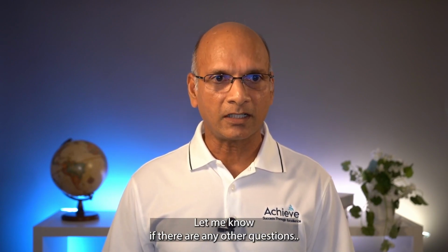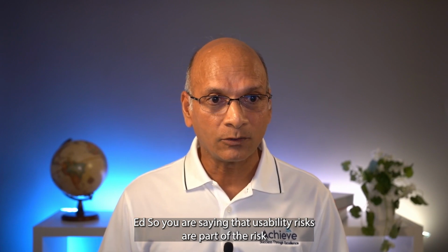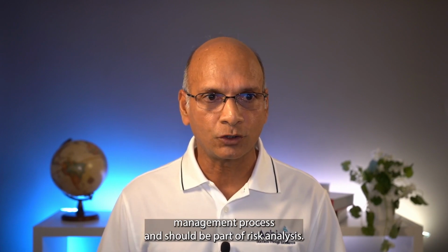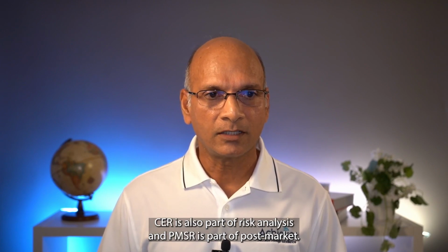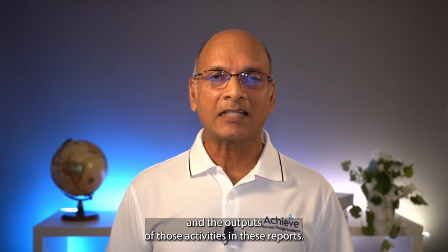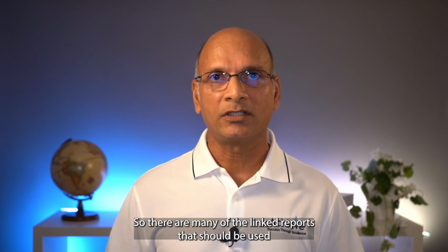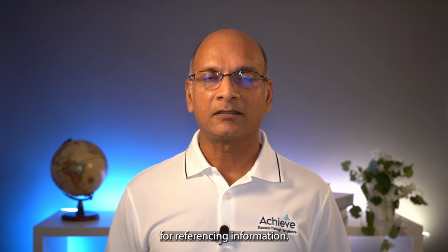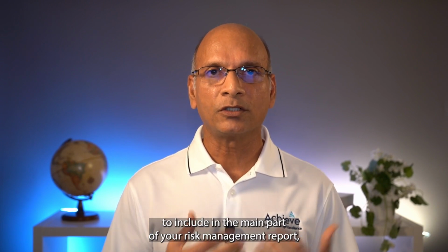Let me know if there are any other questions. Ed, looks like you have another comment. Sorry, I missed it. Ed, so you are saying that usability risks are part of the risk management process and should be part of risk analysis. CER is also part of risk analysis and PMSR is part of post-market. So you see, you are building linkages between different activities and the outputs of those activities in these reports. So there are many other linked reports that should be used for referencing information. Maybe you extract some of the conclusions and summary from those reports to include in the main part of your risk management report. You could consider that.